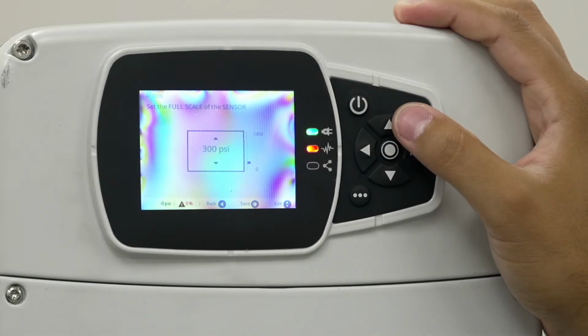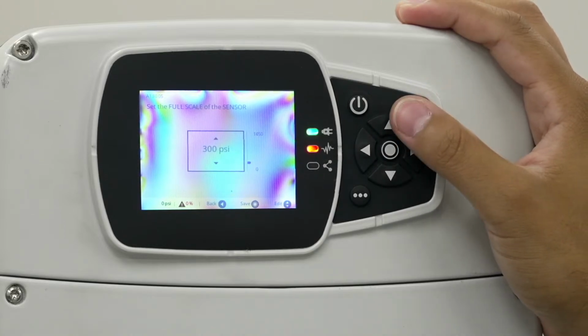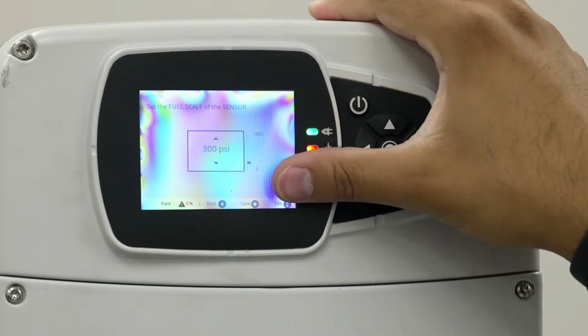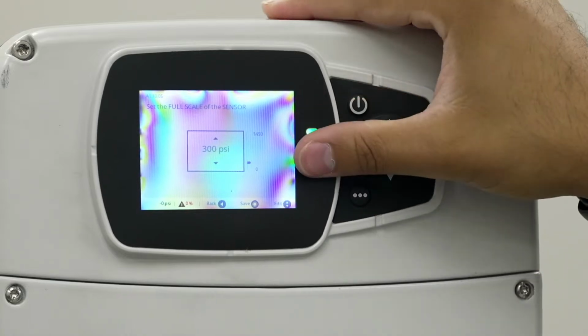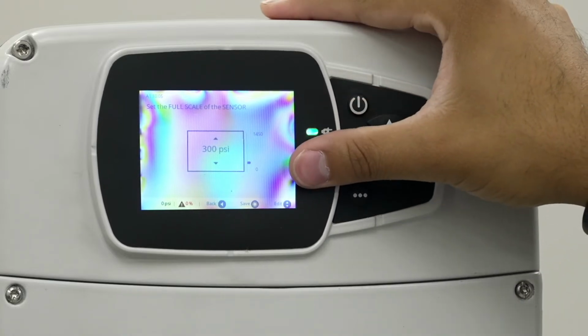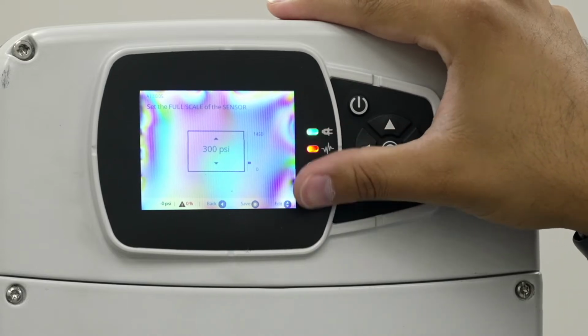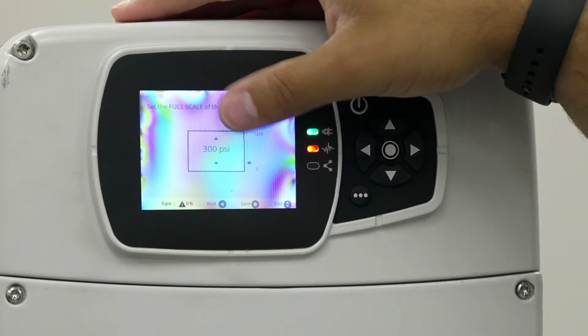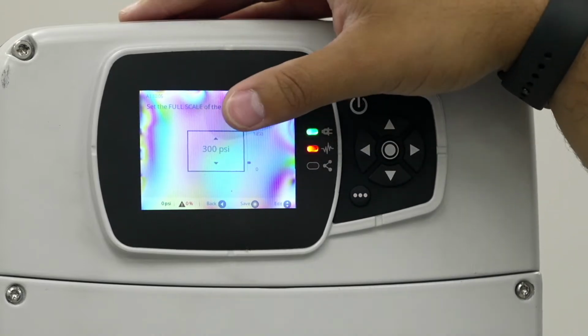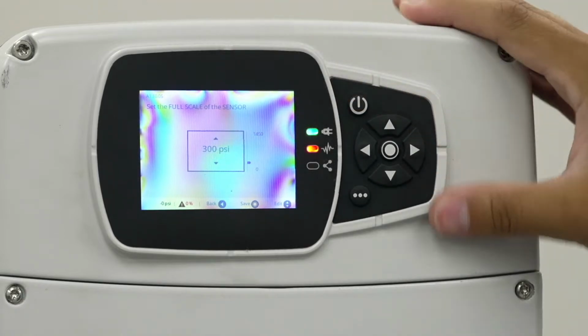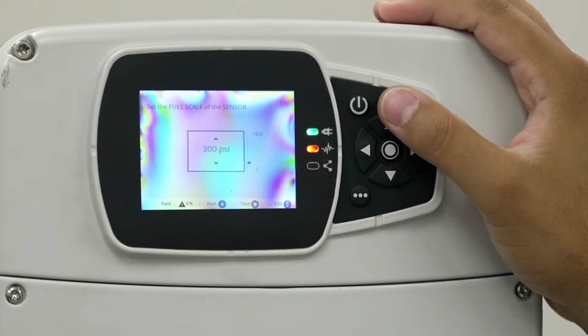Now this is saying the full scale of the sensor. So it's basically just asking what sensor you're using. It's going to come preset here, populated at 300 PSI. As I touched on, we are including a 0 to 300 PSI transducer. But if you had a higher pressure application and you were going to end up using a 0 to 500 PSI transducer, for example, then you would need to adjust this up to 500 PSI to let the unit know the full range of the sensor you're planning on using. Or you'll get inaccurate pressure readings back to the VFD then.